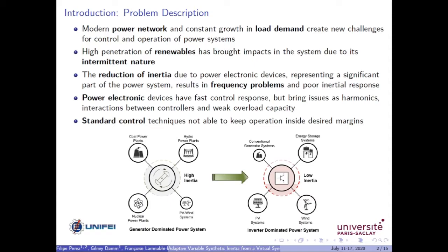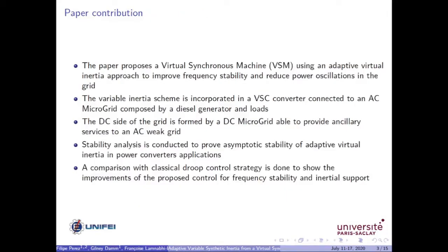The power electronic devices have a fast control response, but they also bring harmonic issues, interactions between controllers, and a weak overload capacity. So in this context, the standard control techniques are not able to keep the system in the desired margins of stability. The transformation of a high inertia system to a low inertia system is based on the power electronic devices introduced in this grid. In this way, the paper contribution is to propose a virtual synchronous machine using an adaptive virtual inertia approach to improve the frequency stability and to reduce the power oscillations in the microgrid.